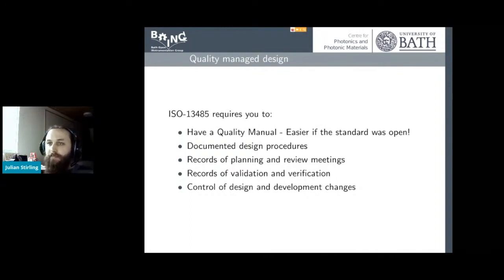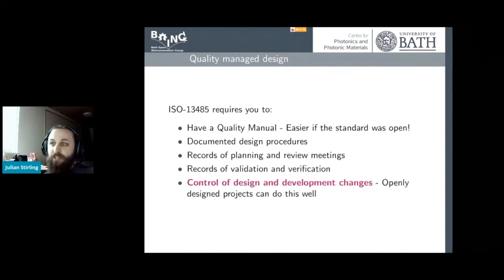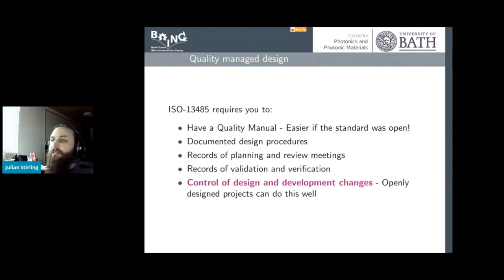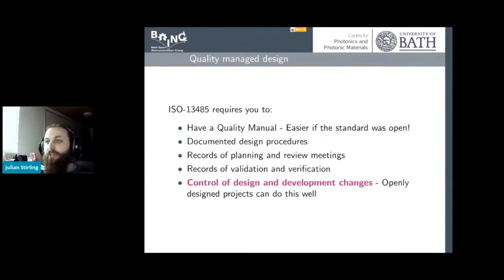A big part of ISO 13485 is control of design and development changes. This is something that projects that design in the open can do very well — a lot of them are on GitHub or GitLab, so you've got a copy of the design over time. And importantly, all of the changes have hopefully been discussed in the open, so you've got more than just the design over time — you've got why it happened.